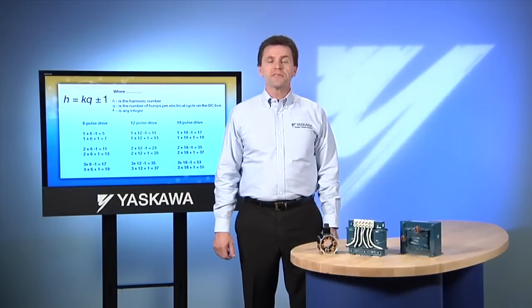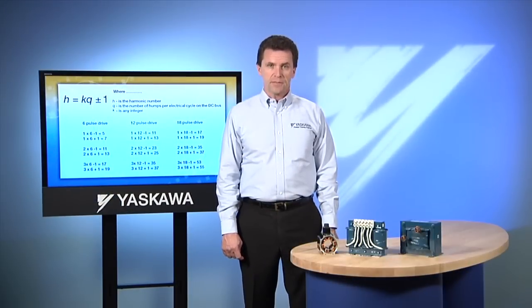The downside of the 18-pulse rectifier approach is that it is usually available only in large-sized drives. A typical 15-horsepower industrial drive isn't available with an 18-pulse rectifier scheme. 6-pulse schemes are most common, and 12-pulse schemes are available in some instances. Large horsepower HVAC drive applications are often held to a very strict conformance of IEEE 519-1992 and may benefit from a VFD with a 12-pulse rectification scheme.